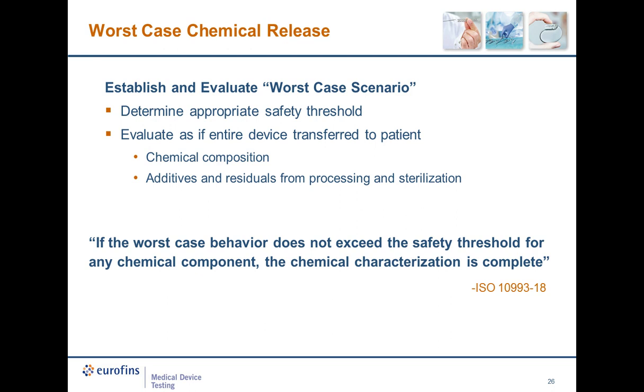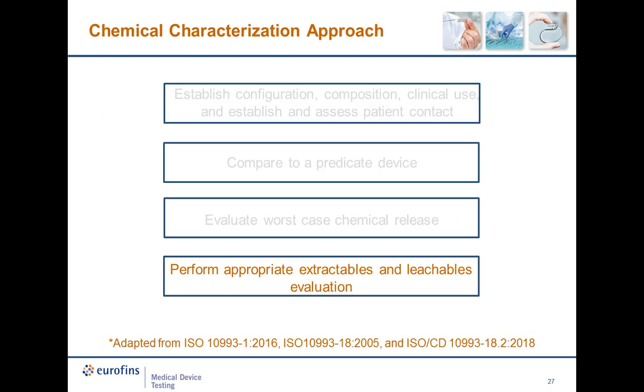After establishing the safety threshold, the sponsor should then perform an assessment comparing the qualitative and quantitative information on the composition of all of the materials of the device, including the processing materials, against the safety threshold. If the sponsor can demonstrate that even when all constituents of the device are introduced to the patient, there is no safety concern for the patient, then the chemical characterization process is complete.